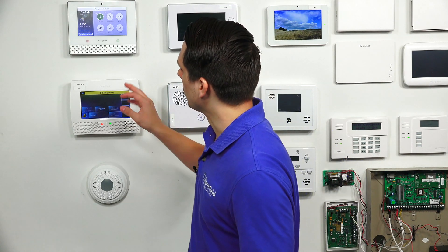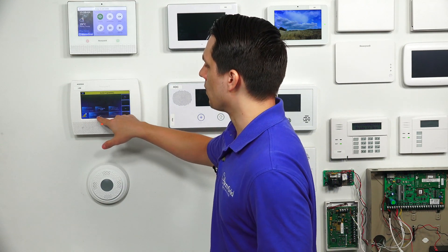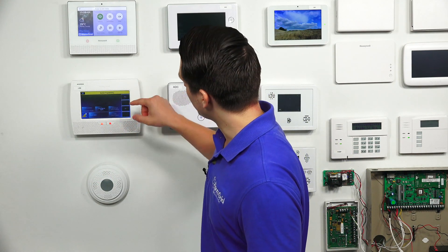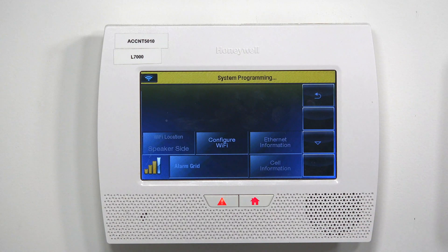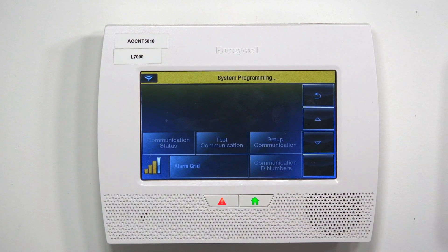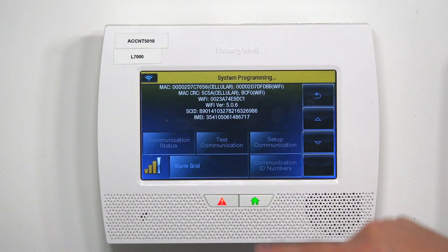This is actually where you would normally configure the Wi-Fi — input the password, find your network, stuff like that. So once you have input the Wi-Fi information and have it set up, you will be able to see your Wi-Fi network at the bottom left with a couple of bars showing you the signal strength. To find the MAC address, hit the down arrow and you're going to see Communication ID numbers — tap on that and this will show you the MAC address.